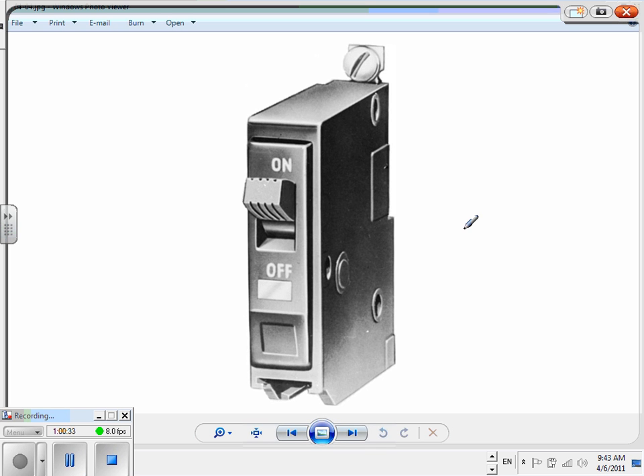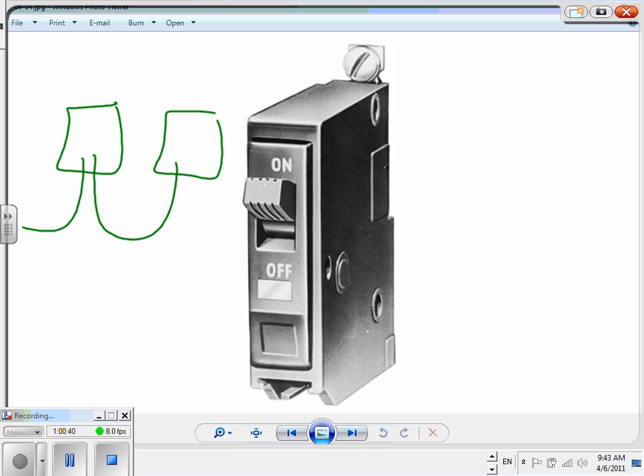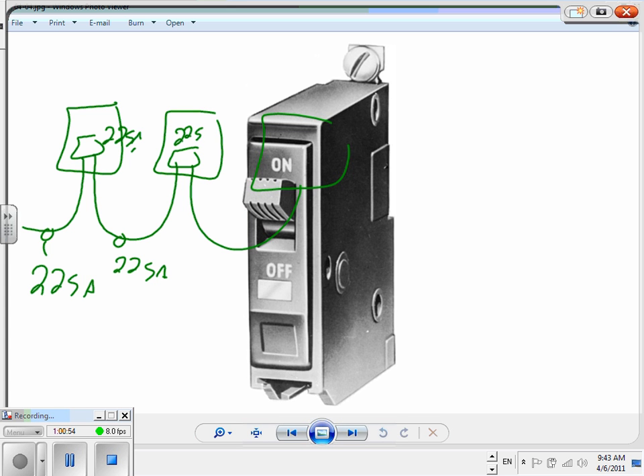So here's panel number 1, guys. Panel number 2. I can come up with a feeder in, feeder out, and panel number 3, feeder out again. Each one of these is 225 amp. I have a circuit breaker 225 amp. The feeder here 225 amp. I have another circuit breaker 225 amp. And another circuit breaker here 225 amp. And a cable 225 amp. So I have a 225 amp feeder that feeds 3 panels.